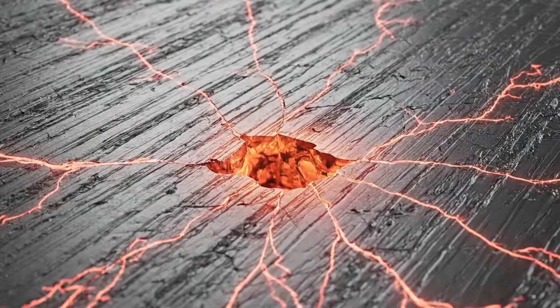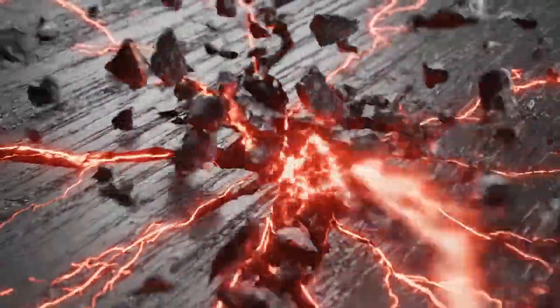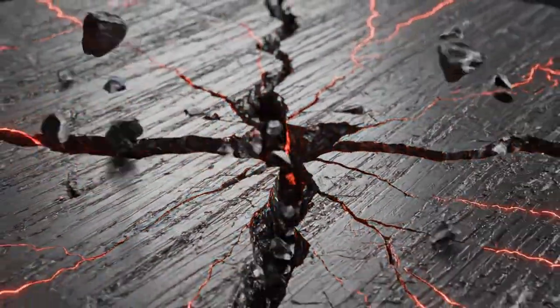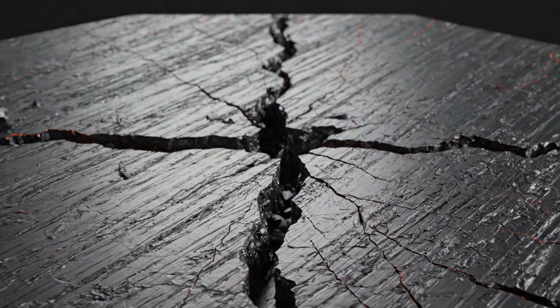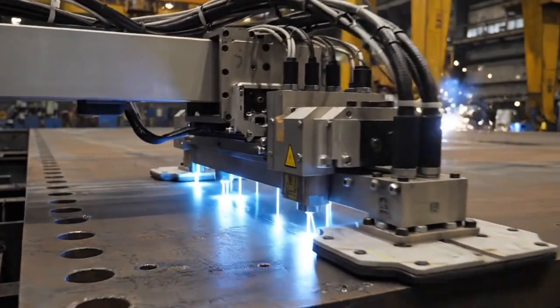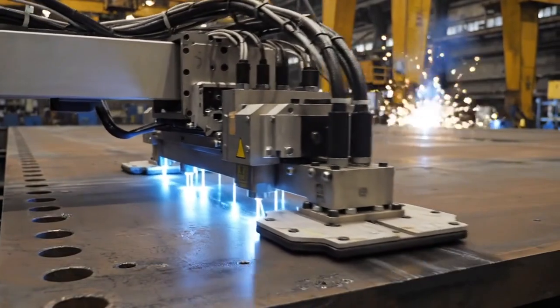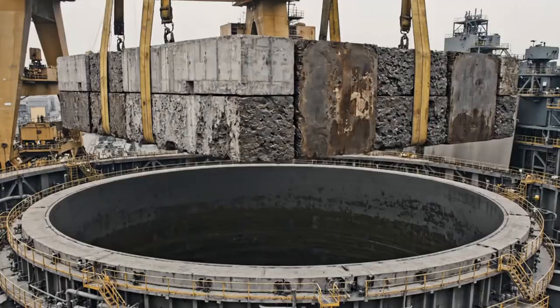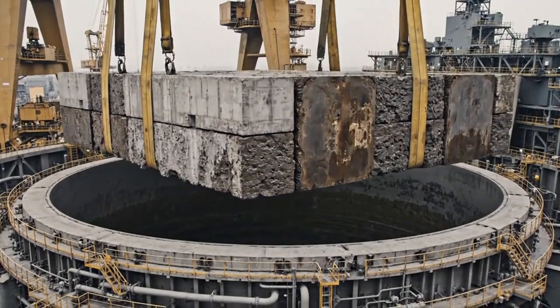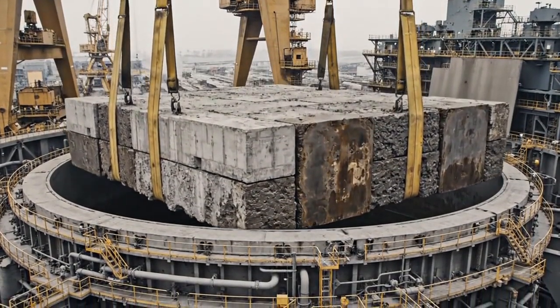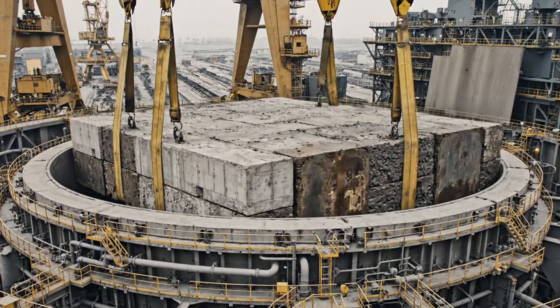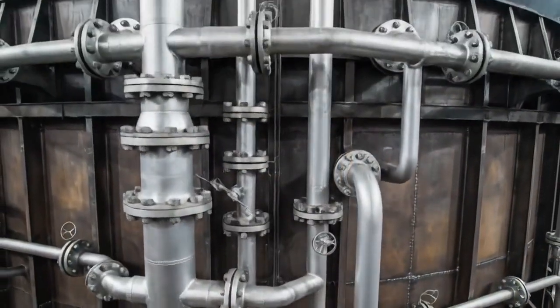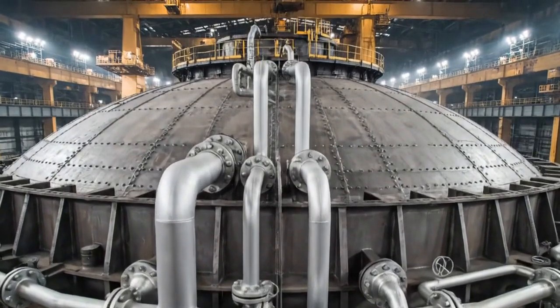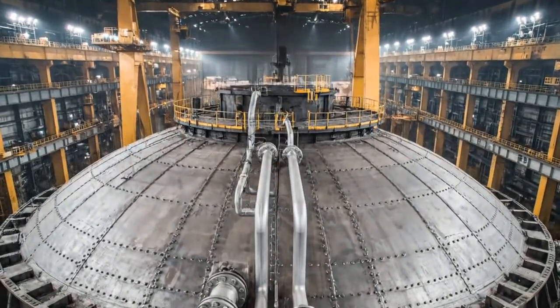welding process. Even a void measuring a fraction of a millimeter can act as a stress concentrator, propagating into a catastrophic shear fracture under the relentless thermal cycling of a 50-year operational lifespan. Furthermore, automated ultrasonic phased array scanners are deployed to detect internal delamination within the steel plates themselves. This is followed by the installation of the biological shielding: heavy layers of lead plate, high-density concrete, and borated polyethylene designed to absorb stray neutron flux. Only when the atomic structure of the entire containment system is proven completely flawless is the reactor certified for fueling.